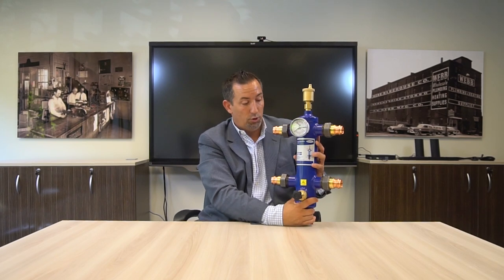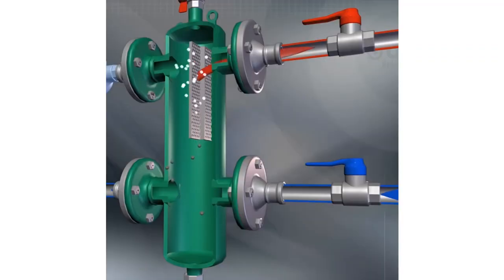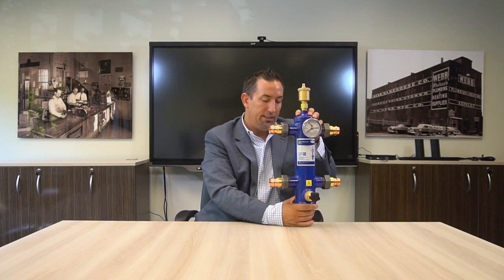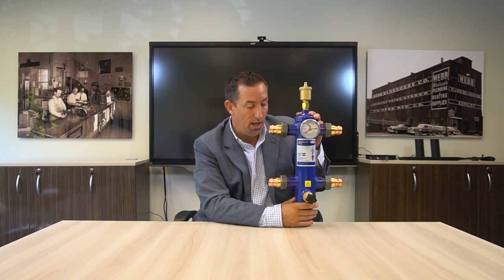Why is hydraulic separation so important, and what is hydraulic separation? Hydraulic separation is referred to in many different ways. It's often called decoupling the system. Sometimes it's called primary secondary piping. Essentially what it's allowing is for the boiler to get the flow it needs, but also the system zones and piping to get the flow that they need. And they can operate independently of each other. When this is sized correctly, it eliminates any piping equation that could lead to an improper install. You're guaranteeing that your boiler piping is done correctly first time, every time, eliminating callbacks and saving you time and money.